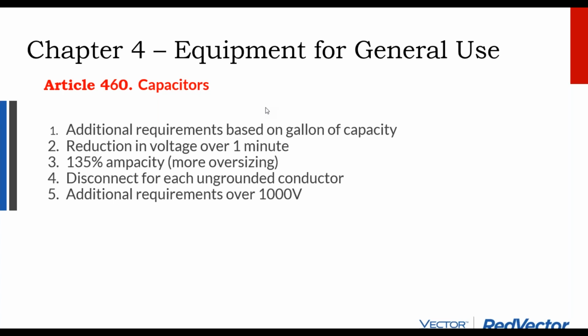And there's differences between continuous output that's running full time and intermittent output that is maybe running for 3 hours or less. In the beginning parts of code, we see that a lot of stuff is sized to be either 100% of the intermittent output, the discontinuous output, or an additional 25% for continuous load. With capacitors, it's a special thing where they say the conductors have to be 35% rather than 25%.